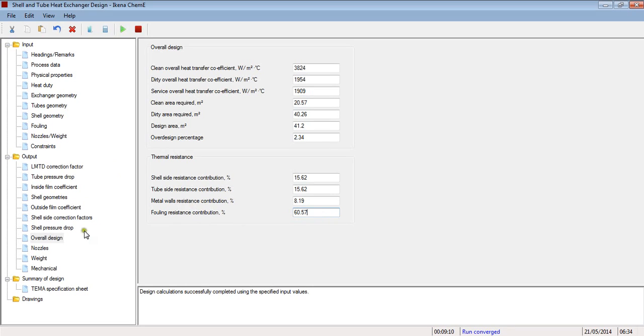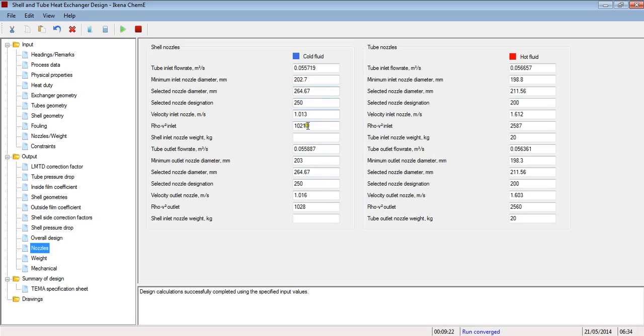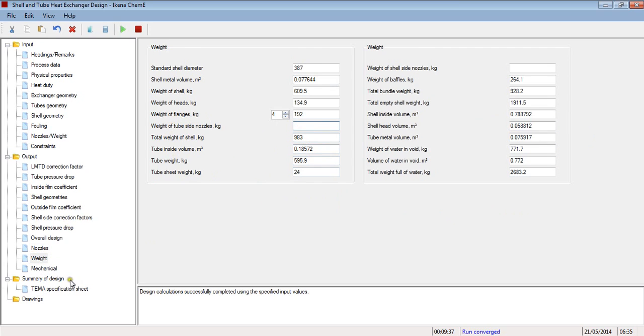Okay, so as I mentioned previously, a good design will try to maximize the use of pressure drop and increase the heat transfer coefficients. Nozzles, here you have information about the nozzles. I don't know why these have not calculated, but I will need to look into that. But this looks fine. Rho v square looks fine. Same here, this is good. This is good. Weight of the heat exchanger, again, since this nozzle weights are not there, it's not come up here either, so that's fine. Weight of the heat exchanger with water in it is 2683. Empty heat exchanger weight is about 1900 kg.